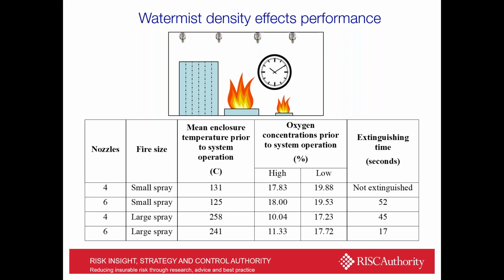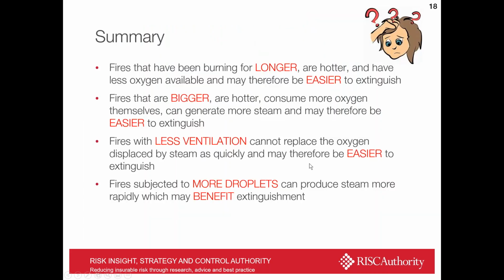We've already seen that. But on a small spray fire, we can see that with 6 nozzles operating, the fire will be extinguished in 52 seconds. But if it comes down to just 4 heads operating, again, we reach a threshold where the fire doesn't extinguish. So hopefully, if you've managed to get your head around that, it is confusing. It demonstrates just how confusing things can be.